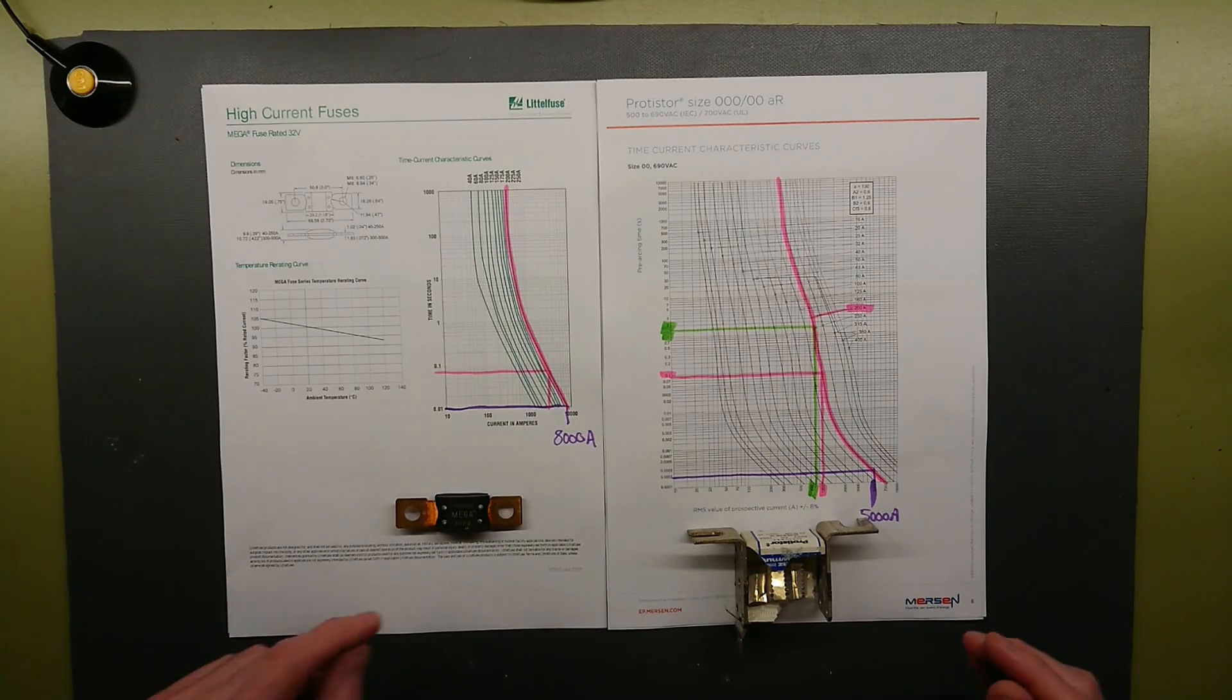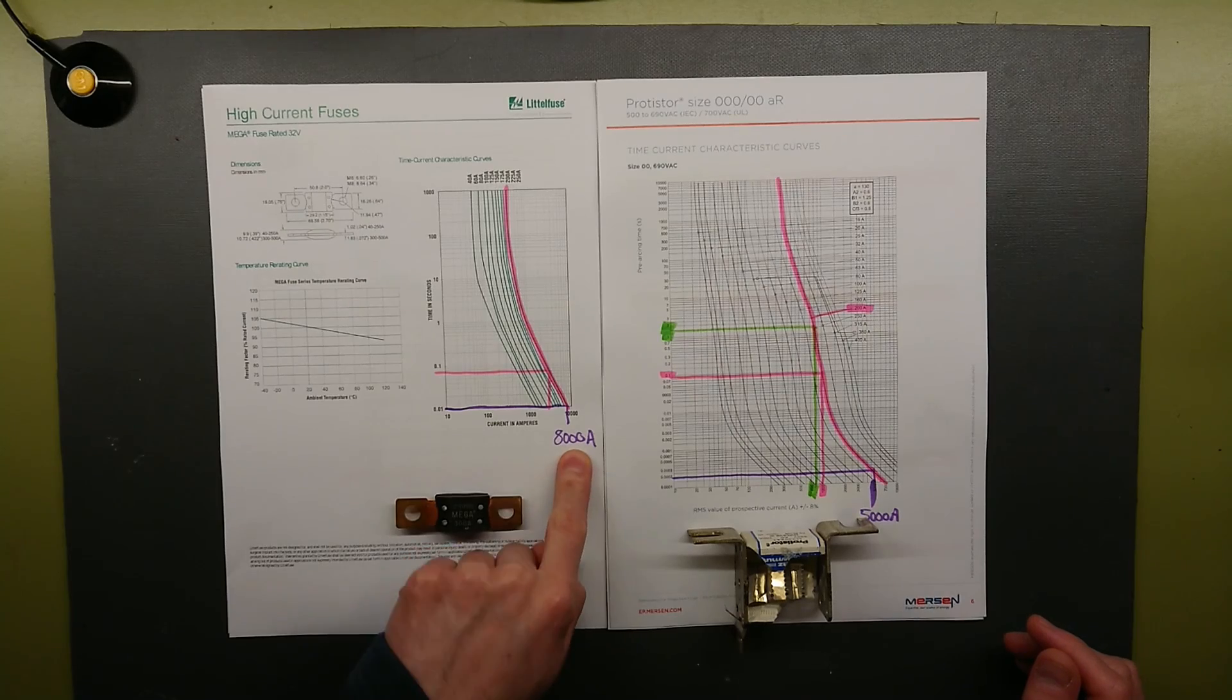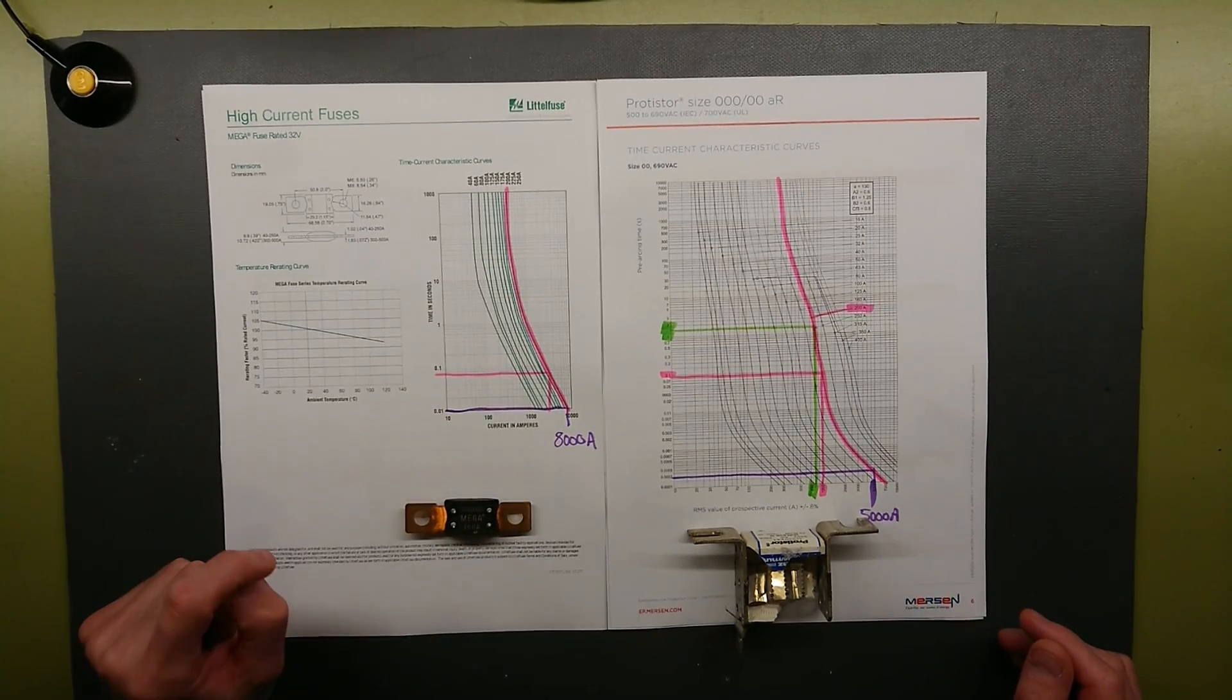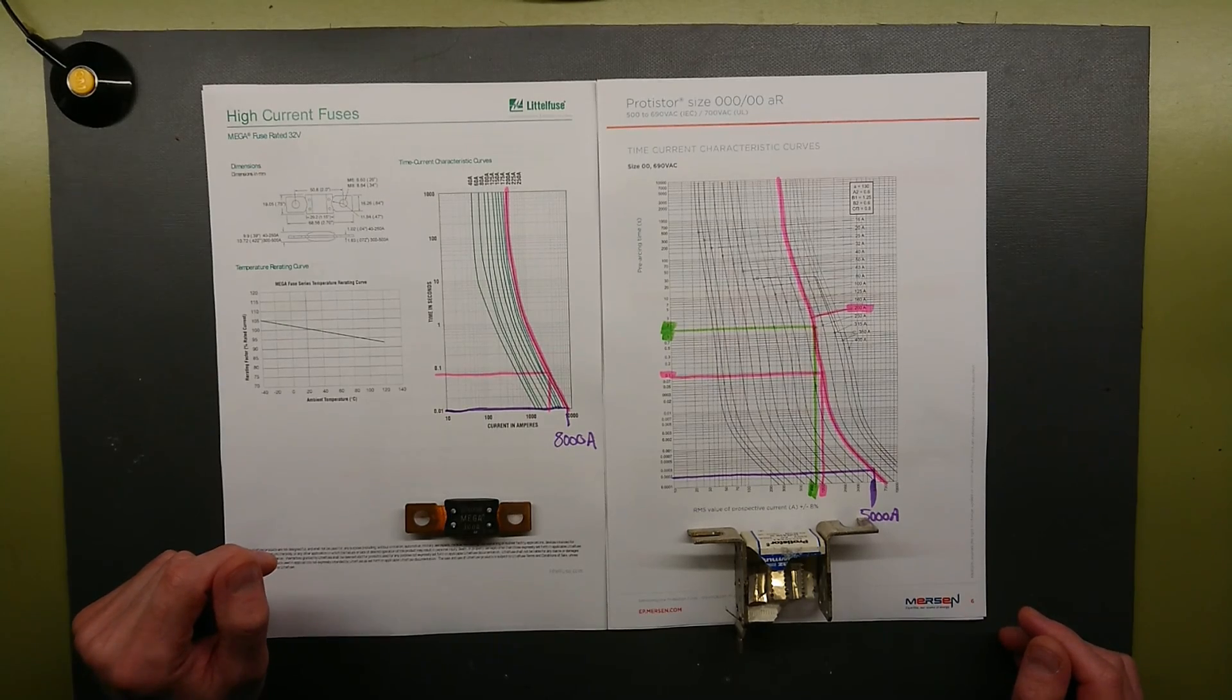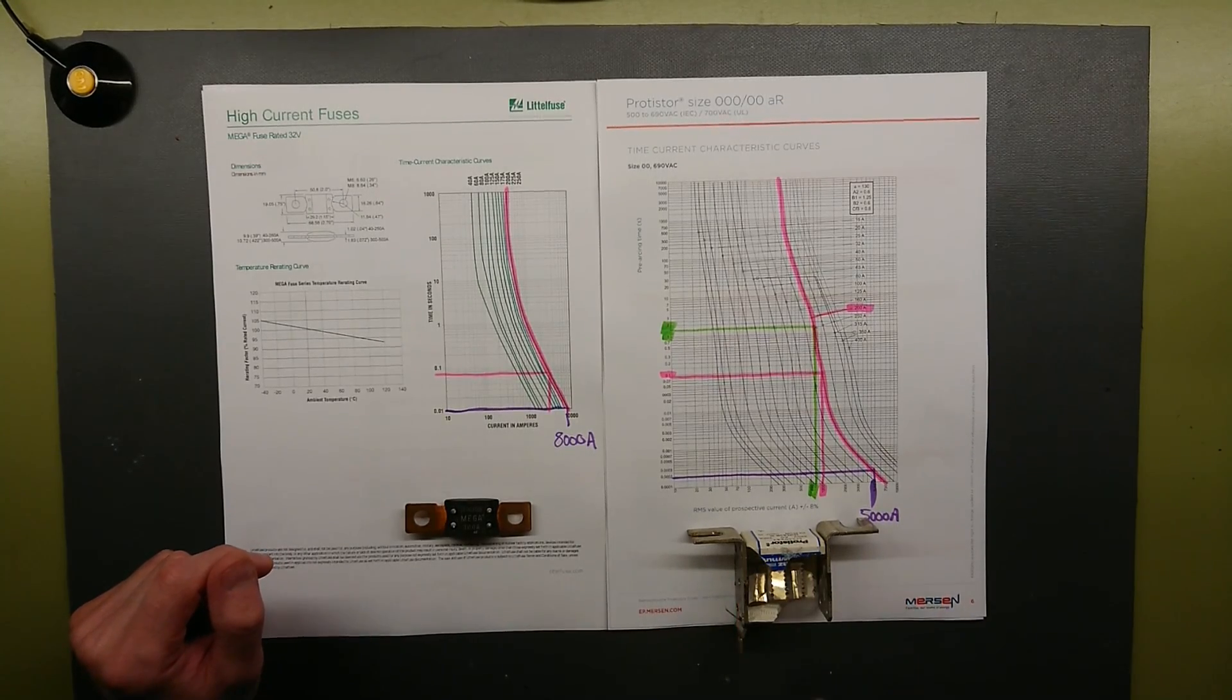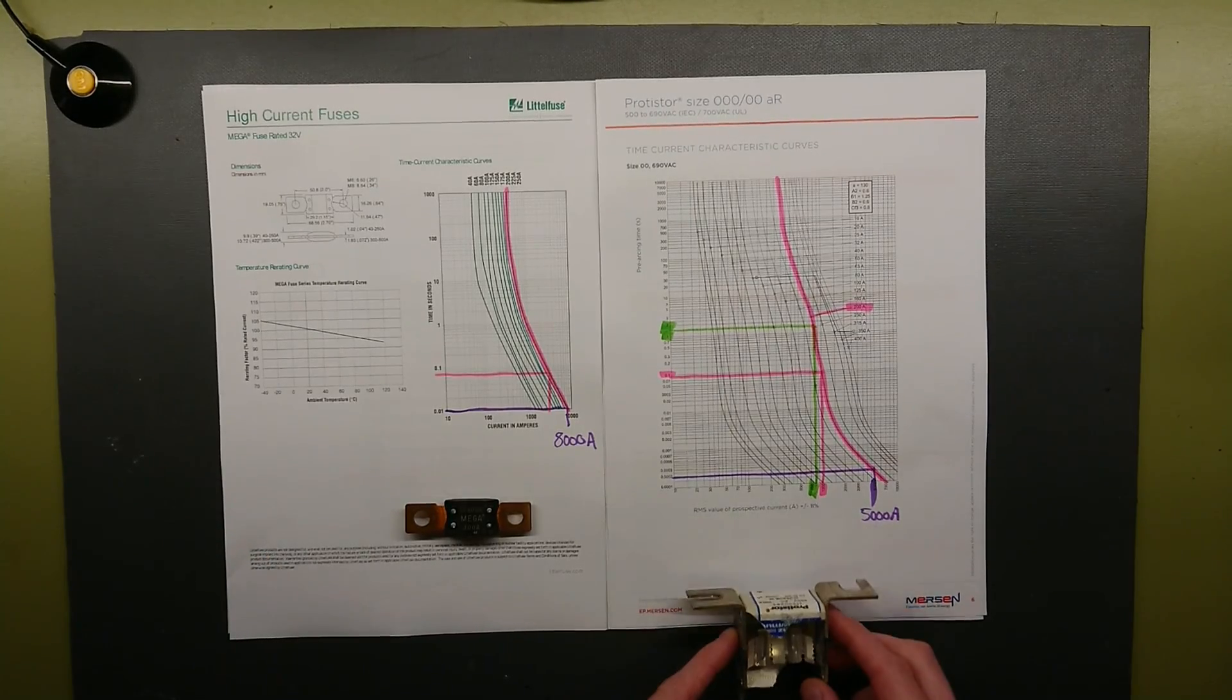But if we take 25 times the rated current, we come up to 8000 ampere for the DC fuse. It would still take 10 milliseconds to melt.